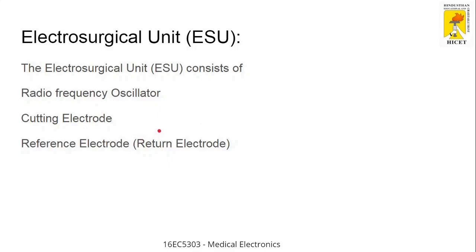The reference electrode is the return electrode. In electronics, you always have two potentials — a lower potential and a higher potential — and both are important to complete the circuit. Just as a light has a positive terminal and a negative terminal, current flows from higher potential to lower potential. Similarly, for heat to effectively cut tissue, it must flow from higher potential to lower potential, and that is why a reference electrode is needed.